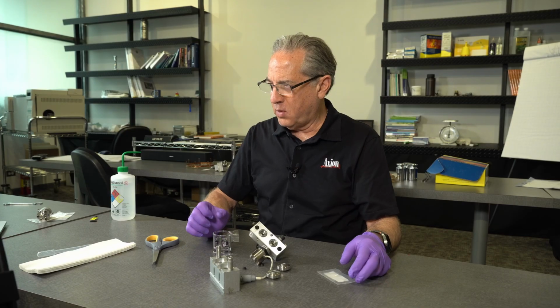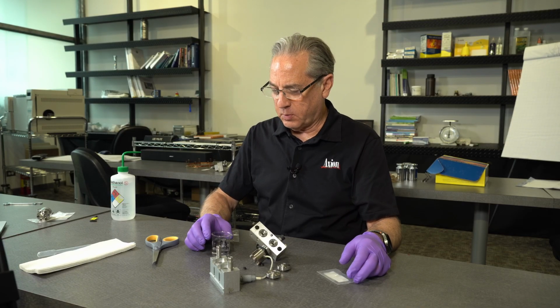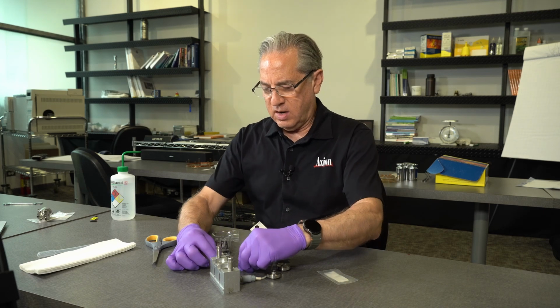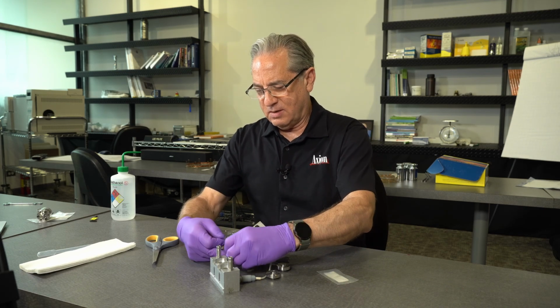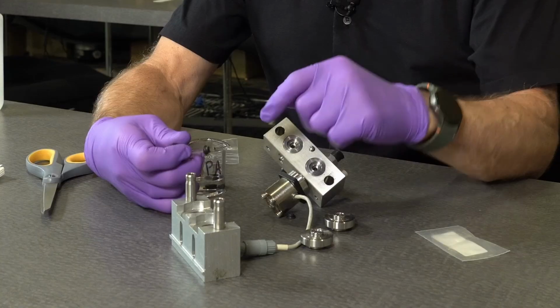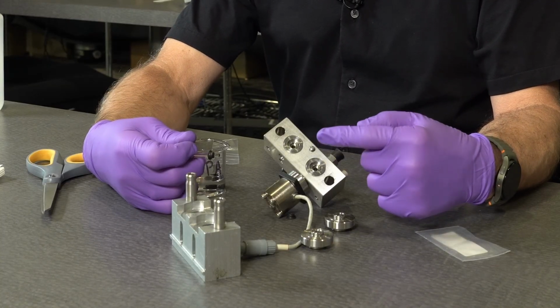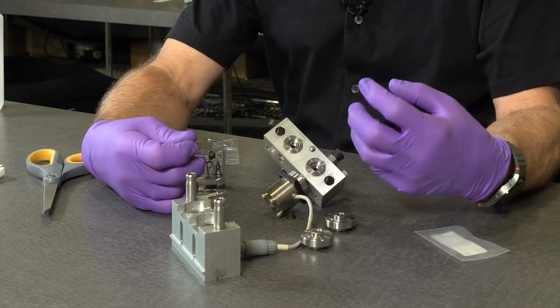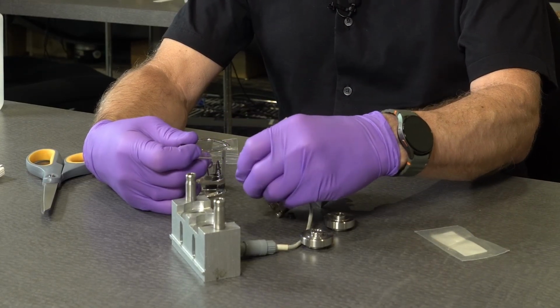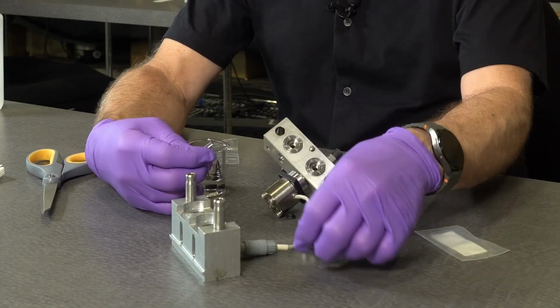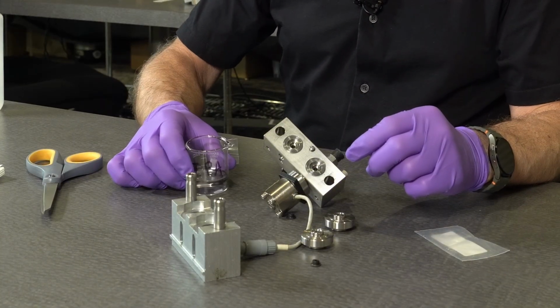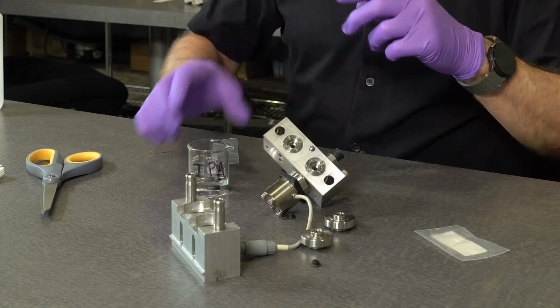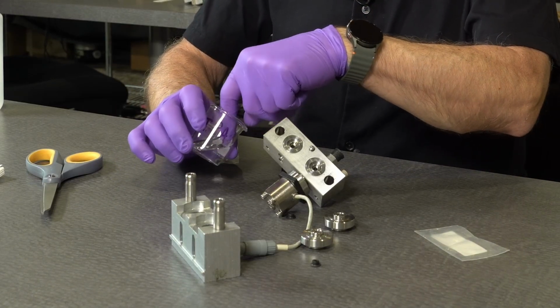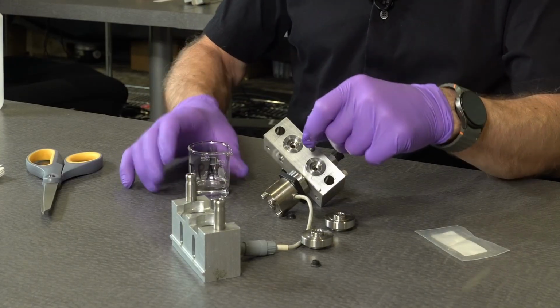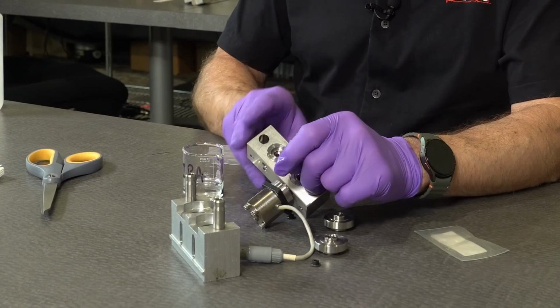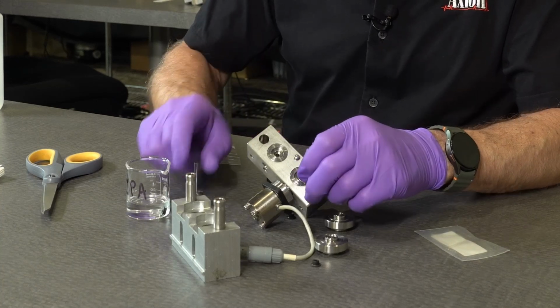What I really want is I want them to be wet with isopropanol. So the reason is when the piston seal makes the seal itself, it's not really plastic against sapphire, it's really a layer of liquid in between the plastic and the sapphire, and that is the seal material. You've heard the term priming a pump. Well, the reason you would prime a pump is to make sure there's liquid in there. So my trick is I make sure they're really wet before I even start the procedure, and then when I put them in, guess what? There's already a layer of liquid. I like isopropanol, and the reason is isopropanol is what we call a universal solvent. It could wet any surface.